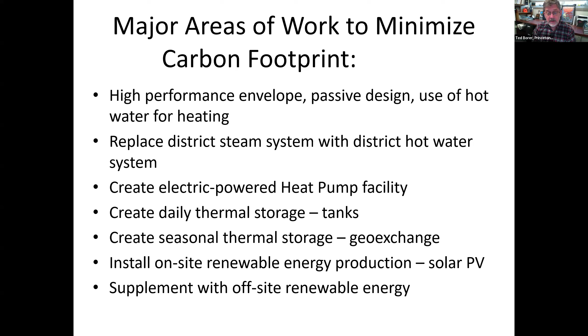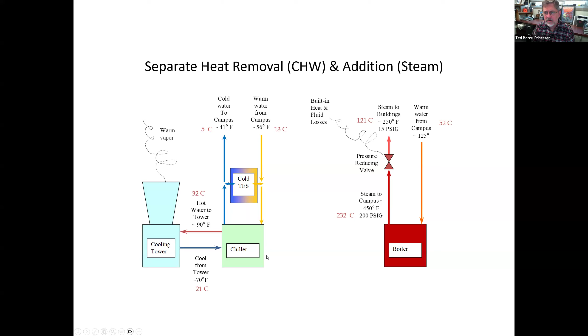On the right-hand side, we're burning stuff, delivering heat to the campus. On the left-hand side, we're adding more energy to this system and removing heat from campus and throwing it away. So you say, well, gosh, you really ought to combine those two systems so you could be a lot more efficient. So that's what we're doing. We're putting a heat pump in the middle, but the heat pump isn't enough to make the steam conditions of today, so we're making hot water.